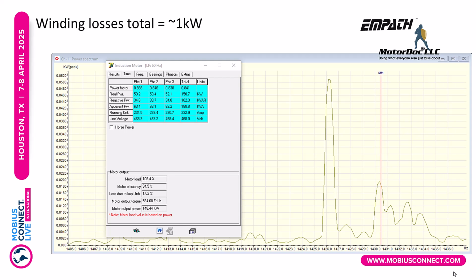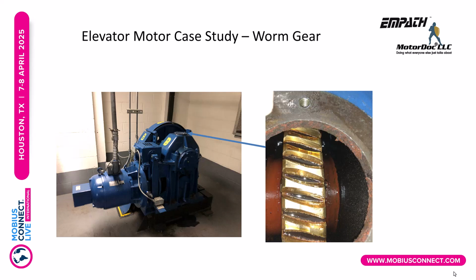And we can see the losses associated with that by converting it over to a kilowatt spectrum. In this case, you can see it's about a kilowatt with all of these peaks that are associated. With those peaks and some other stuff going on, all the peaks added together come out to be about a kilowatt. And the direct result of that, 1 kilowatt times 6,000 hours, say, comes out to be about 4 tons of CO2. And we'll talk about how to calculate that in a bit.